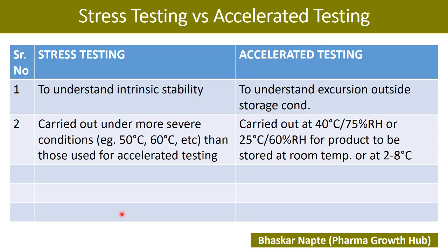The second point for accelerated testing: accelerated testing is generally conducted at 40 degrees Celsius and 75% RH if your product is proposed to be stored at room temperature. Alternatively, accelerated testing can be conducted at 25 degrees Celsius and 60% RH if your product is proposed to be stored at 2 to 8 degrees Celsius. These two possible accelerated conditions are purely based on your proposed storage condition.